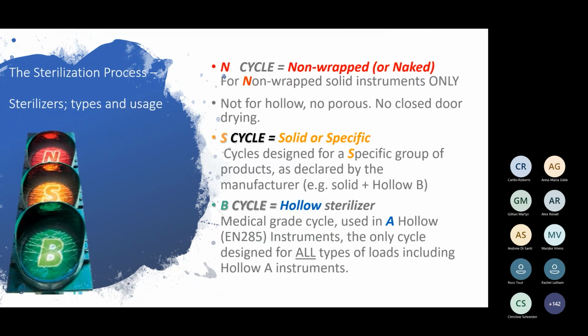There are 3 different types of sterilizers around. An N class you should not see anymore, and I hope nobody still has one, and that is a machine that you can't process any hollow or porous loads in, and it doesn't have a closed door drying. So that means that you have to actually crack the door open for the load to dry. That is not up to standard anymore.